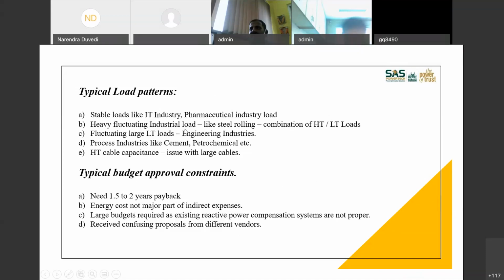Heavy fluctuating industrial loads like steel rolling, a combination of HT and LT loads, the rubber industry, all these are heavily fluctuating loads. Loads can vary from 500 kilowatt to 5 megawatt every 3 seconds. Such kinds of loads also exist in industry where you need different kinds of solutions. Fluctuating large LT loads, again, engineering industries, process industries like cement, petrochemical, etc. There is another new issue which has come up. I'll explain it in the next slide.